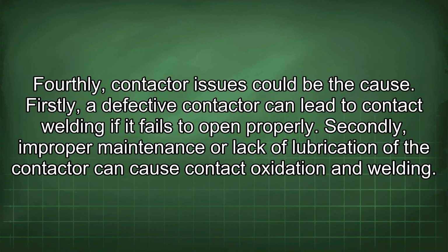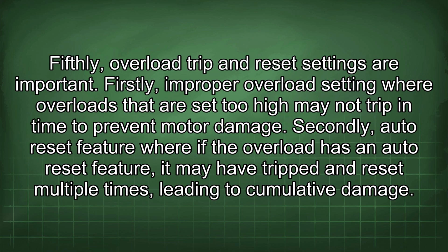Fourthly, contactor issues could be the cause. Firstly, a defective contactor can lead to contact welding if it fails to open properly. Secondly, improper maintenance or lack of lubrication of the contactor can cause contact oxidation and welding. Fifthly, overload trip and reset settings are important.